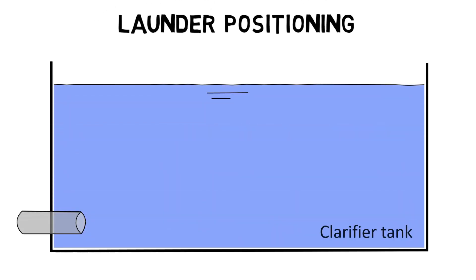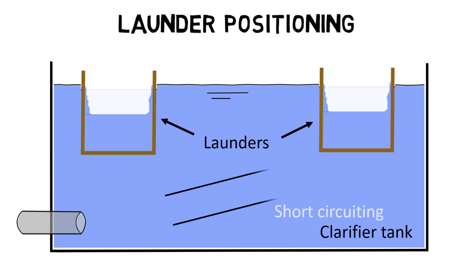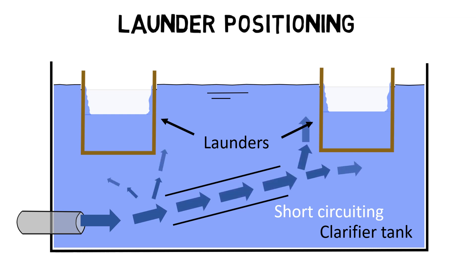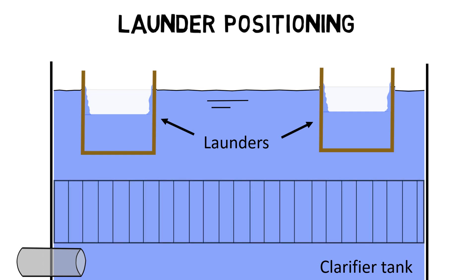Furthermore, the spacing of effluent launders plays an important role in reducing water short-circuiting within the clarifier basin. If the effluent launders are positioned unevenly in the basin, or if the distance between effluent launders is too large, water will flow along a nearly direct pathway from the inlet to the outlet, often resulting in shorter settling times compared with the calculated or presumed detention times. If tube settlers are used, their installation height must also be considered for the effluent launder distances.